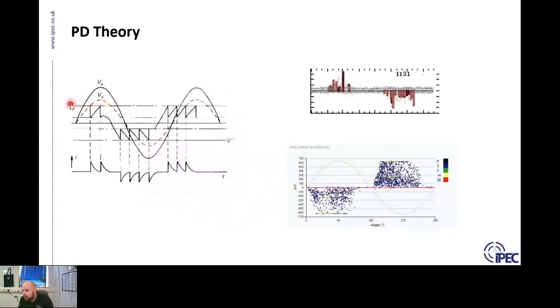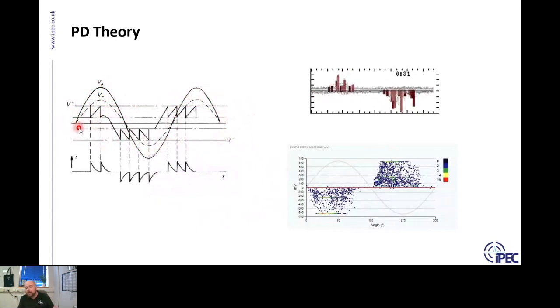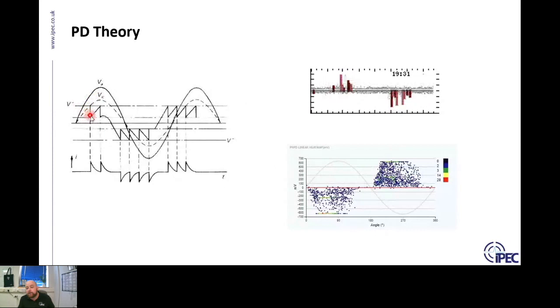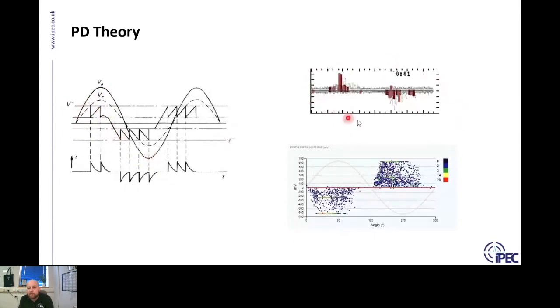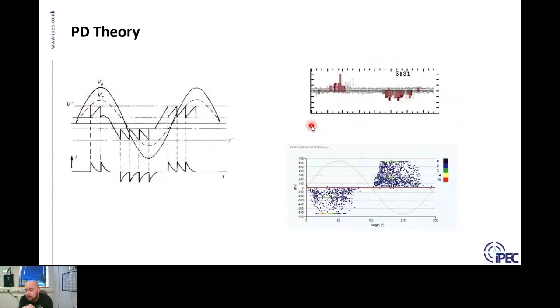If that 17.25 kV threshold is a line on the power cycle sine wave, as the voltage increases the cavity can no longer withstand the stress and a small discharge occurs. The energy keeps increasing, the cavity recharges, and another discharge occurs. So we find that as the energy in the power cycle increases on both the positive and negative sides, partial discharges occur. On the right-hand side is what we call PRPD — phase resolved partial discharge — which is a very common method for users to determine if something is PD or background noise.